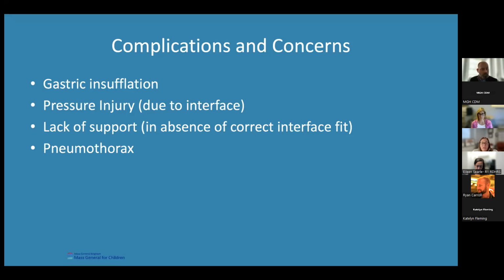There can be a pressure injury on the patient's skin due to a poorly fitting interface. I'll talk about some of the interfaces that are available momentarily, but it's very important, and Krista will go further into this, that you're looking at the blanchableness of the skin, the pressure points that the device is sitting on, and perhaps rotate those if it's not appropriate. You can also have lack of support. These non-invasive systems are built to operate with some degree of leak in the system. It's not a completely closed circuit. So if there is a large leak that goes unnoticed, we could be looking at the ventilator, assuming that the patient's getting a CPAP of 8 or 9, but actually the pressure within the alveolus is not changing because of this large leak around the interface. So the placement and the fit of the interface is incredibly important in delivering non-invasive ventilation.